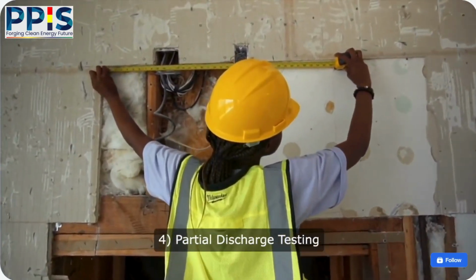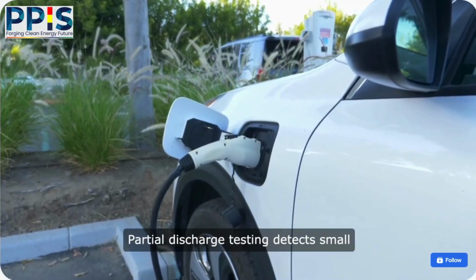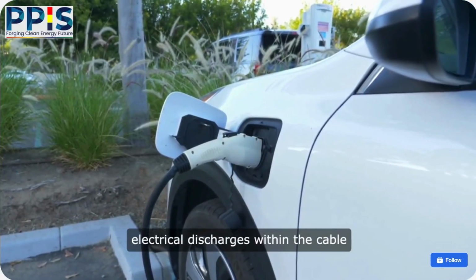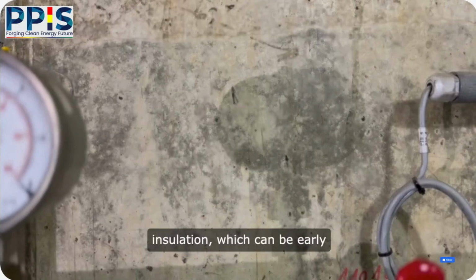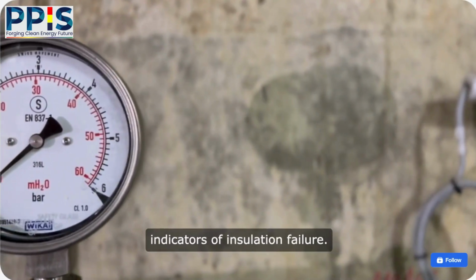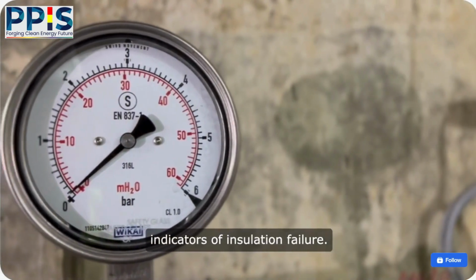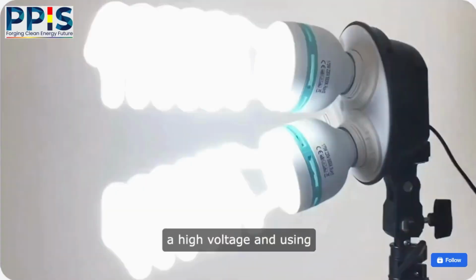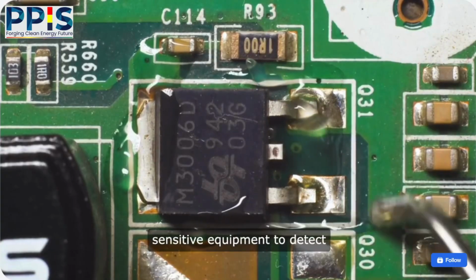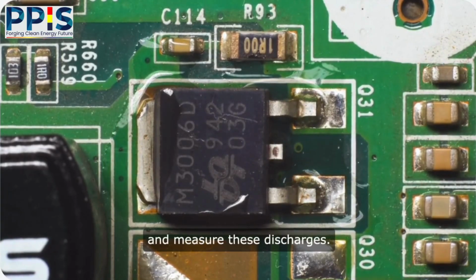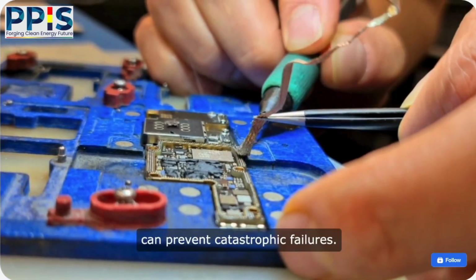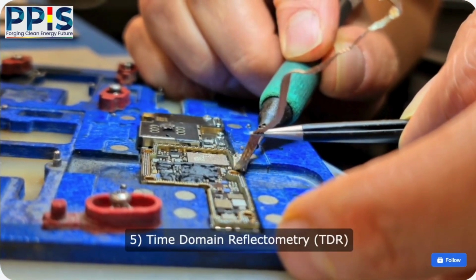4. Partial discharge testing. Partial discharge testing detects small electrical discharges within the cable insulation, which can be early indicators of insulation failure. This method involves applying a high voltage and using sensitive equipment to detect and measure these discharges. Early detection of partial discharges can prevent catastrophic failures.